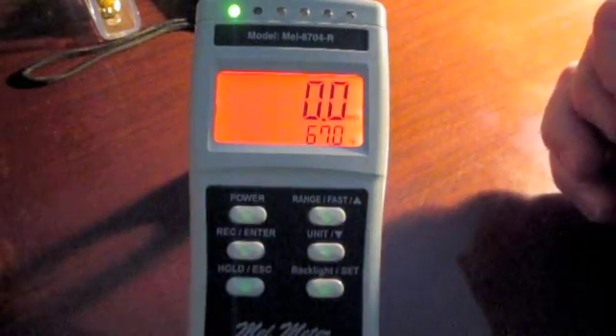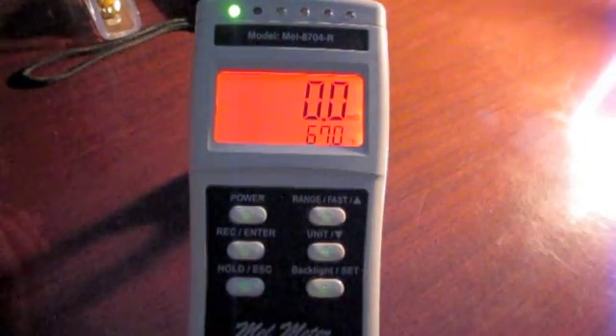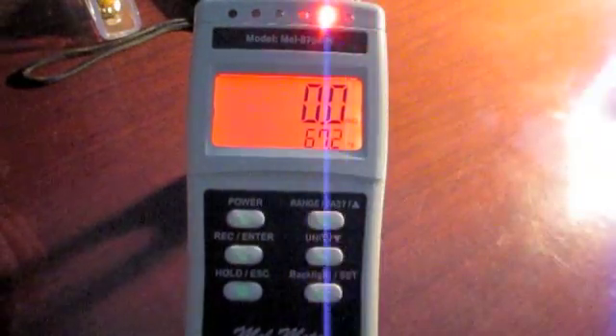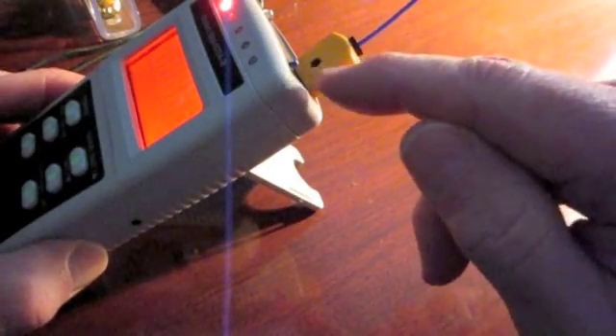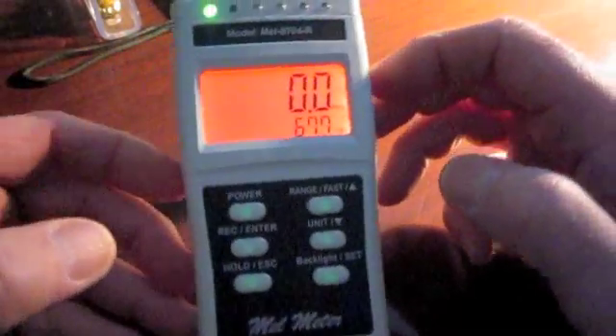Okay. Now, let's go through a temperature increase. To do that, I'm going to touch the temperature sensor. There you go. That's what happens when you go through a temperature increase. Now, eventually, it'll reach its baseline. The thermistor is actually exposed, so the thermal mass of that particular sensor and the insulation around it is very minimal. So, it is a rapid change sensor, and there we are. We're baselined based on the temperature increase I just touched it with my finger.